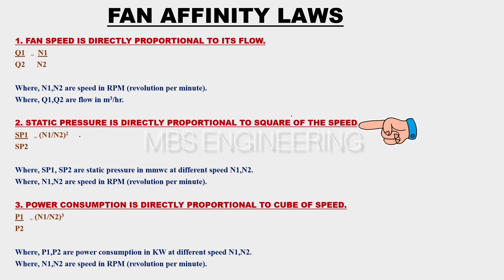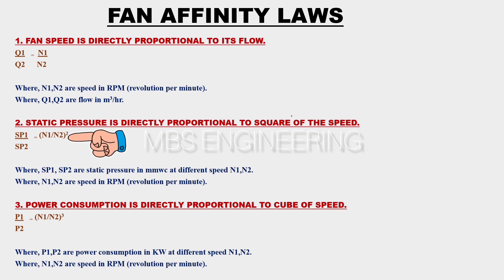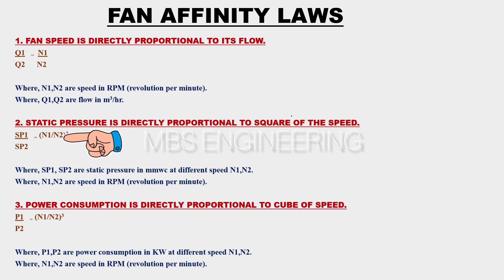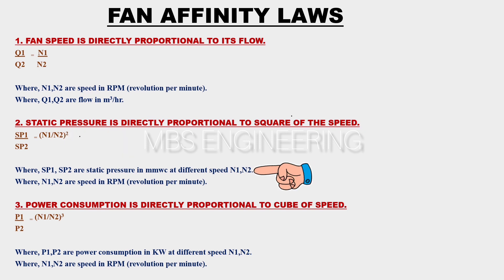The second affinity law for fans: static pressure is directly proportional to the square of the speed. The static pressure SP1 divided by SP2 is directly proportional to the square of speed N1 divided by N2. Where SP1 and SP2 are static pressure in MMWC at different speeds N1 and N2.